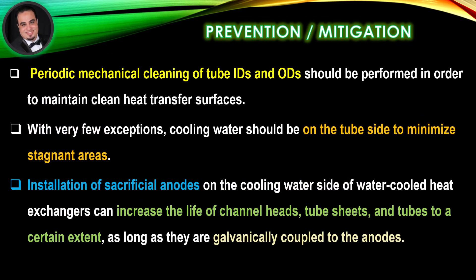Periodic mechanical cleaning of tube inside diameters and outside diameters should be performed in order to maintain clean heat transfer surfaces. With very few exceptions, cooling water should be on the tube side to minimize stagnant areas. Installation of sacrificial anodes on the cooling water side of water-cooled heat exchangers can increase the life of channel heads, tube sheets, and tubes to a certain extent, as long as they are galvanically coupled to the anodes.